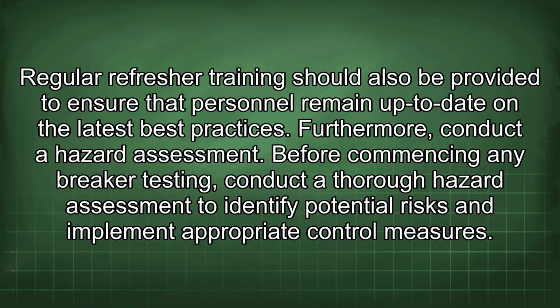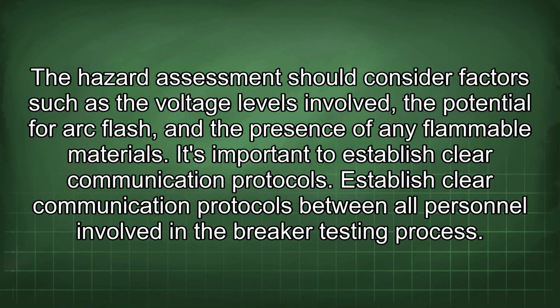Furthermore, conduct a hazard assessment. Before commencing any breaker testing, conduct a thorough hazard assessment to identify potential risks and implement appropriate control measures. The hazard assessment should consider factors such as the voltage levels involved, the potential for arc flash, and the presence of any flammable materials. It's important to establish clear communication protocols.